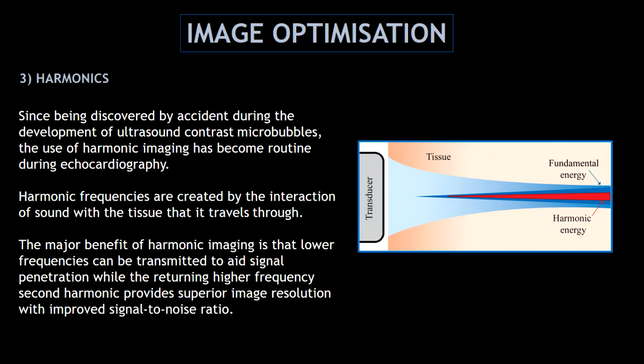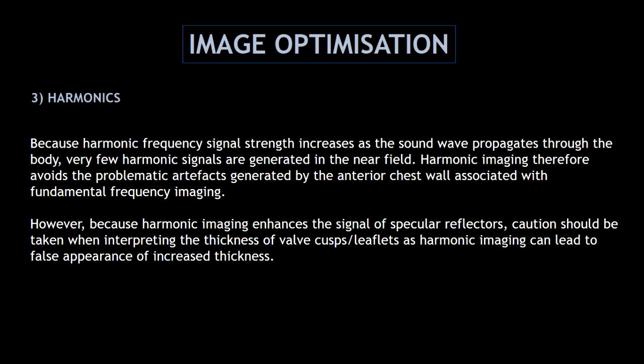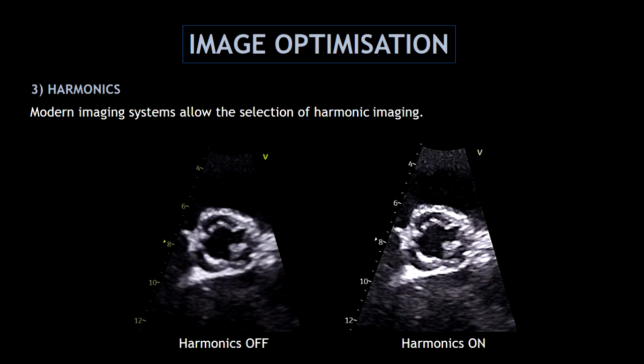Another important feature is harmonics. The harmonics were discovered by accident during the development of contrast ultrasound, and the use of harmonic imaging has become routine during echocardiography. The benefit of harmonics is that it provides superior image resolution, even with lower frequencies. Because harmonic imaging enhances the signal, caution should be taken when interpreting the thickness of the leaflets, as harmonic imaging can lead to a false appearance of increased thickness. The image on the right side is brighter and appears thicker — this is why we have to be careful when interpreting the valves if the harmonics are on.